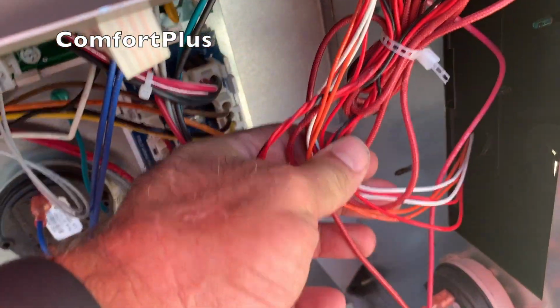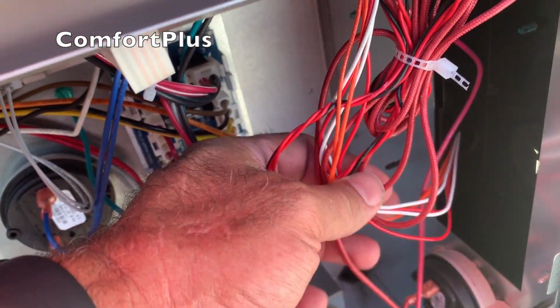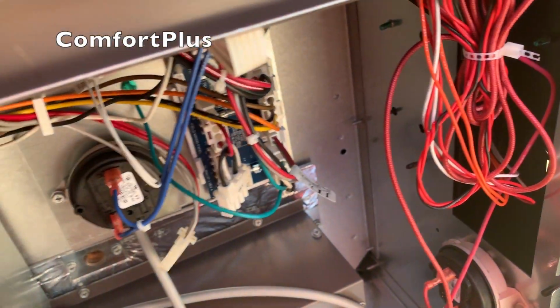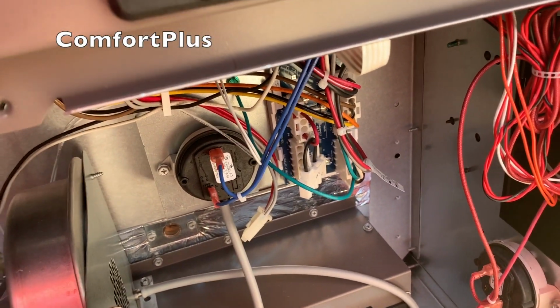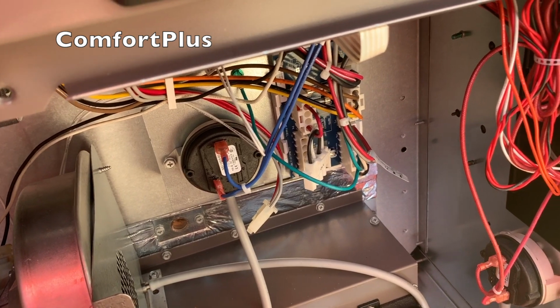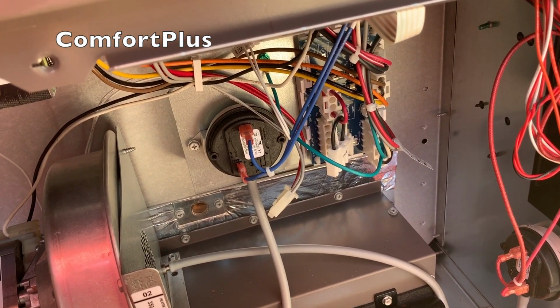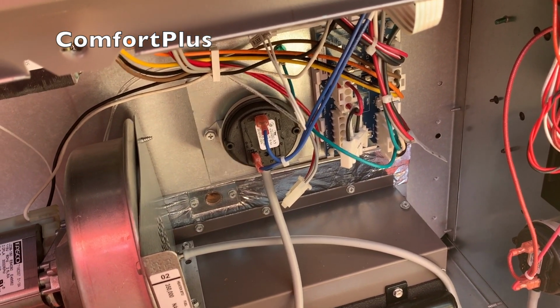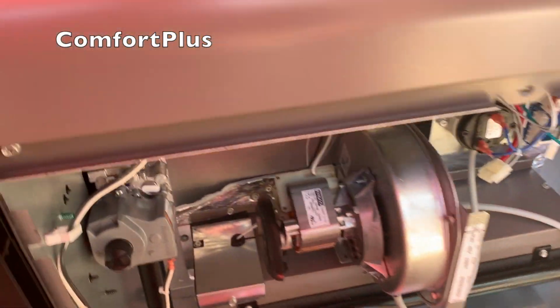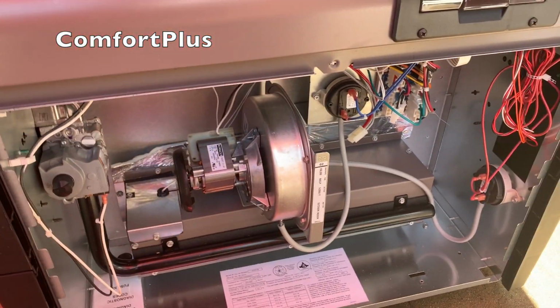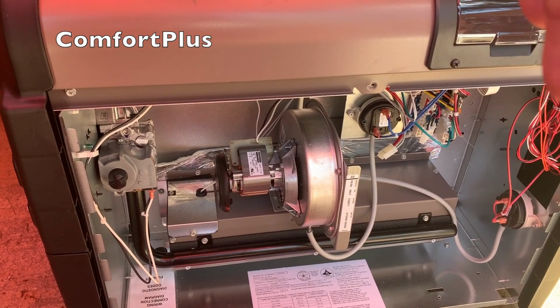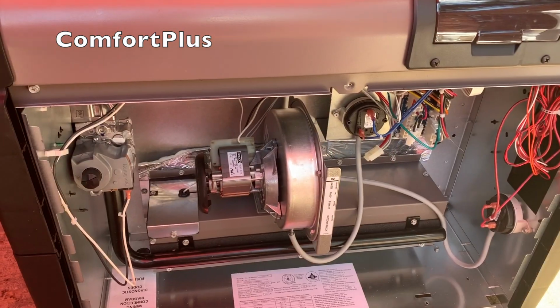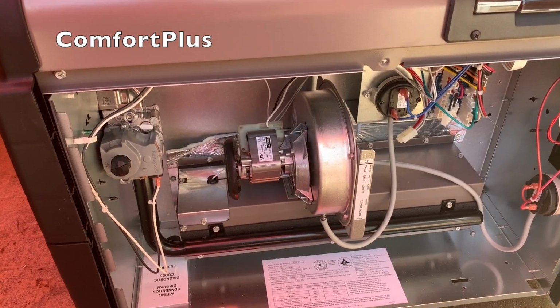There's your typical pressure switch. Should be a water pressure switch, or yeah, somewhere back that way, telling it that it's got flow. Most of these small heaters just use an actual switch that makes on pressure. Some of the larger pool heaters I used to deal with, say 1 million or 1.5 million BTUs, they would actually put a flow switch on them. On ITT units, a big flow switch in the line, which would actually have a paddle on it that would move when water was pushing it.